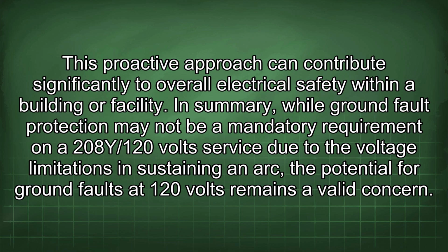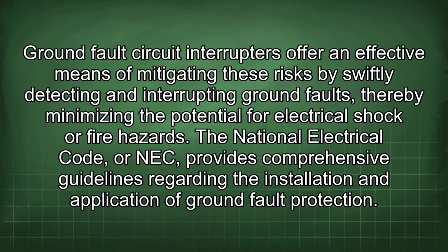In summary, while ground fault protection may not be a mandatory requirement on a 208Y/120 volt service due to the voltage limitations in sustaining an arc, the potential for ground faults at 120 volts remains a valid concern. Ground fault circuit interrupters offer an effective means of mitigating these risks by swiftly detecting and interrupting ground faults, thereby minimizing the potential for electrical shock or fire hazards.